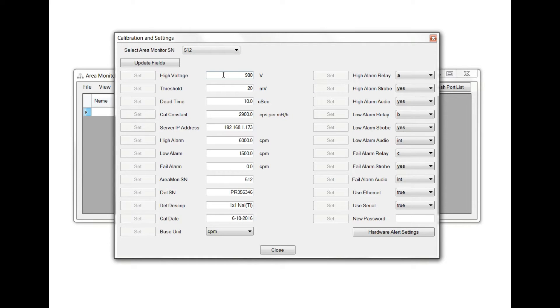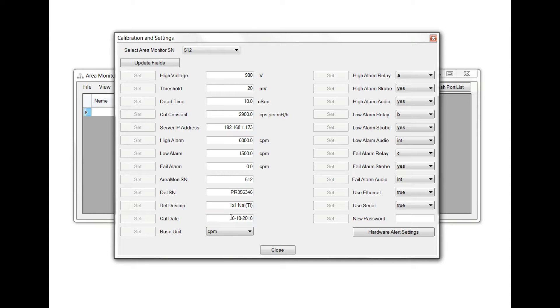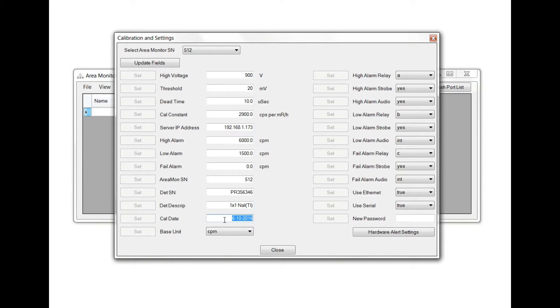It's not recommended that you change the settings of high voltage, threshold, dead time, cal constant, or the serial number and description of the probe. These are all related to the calibration performed on the calibration date. For more information on calibration of your radiation area monitor, contact SE International at SEINTL.com.